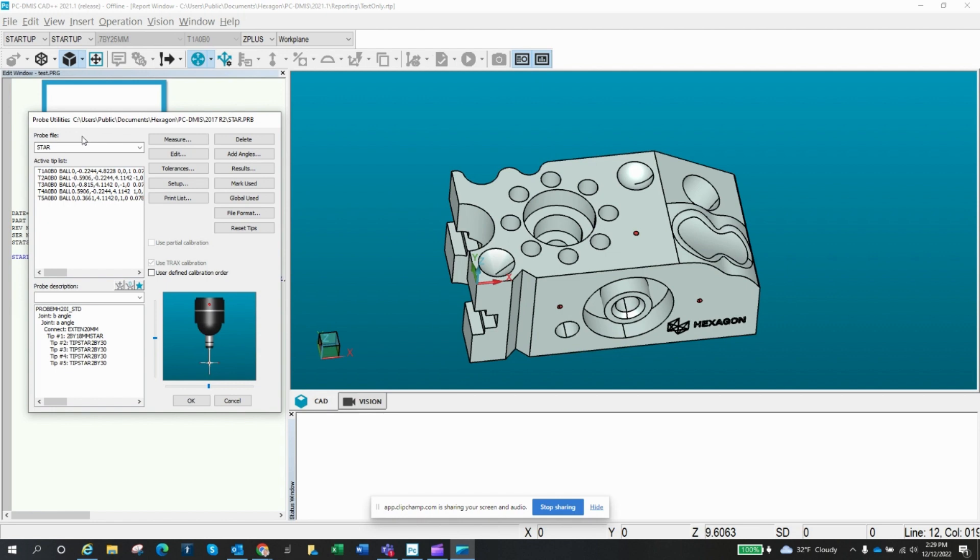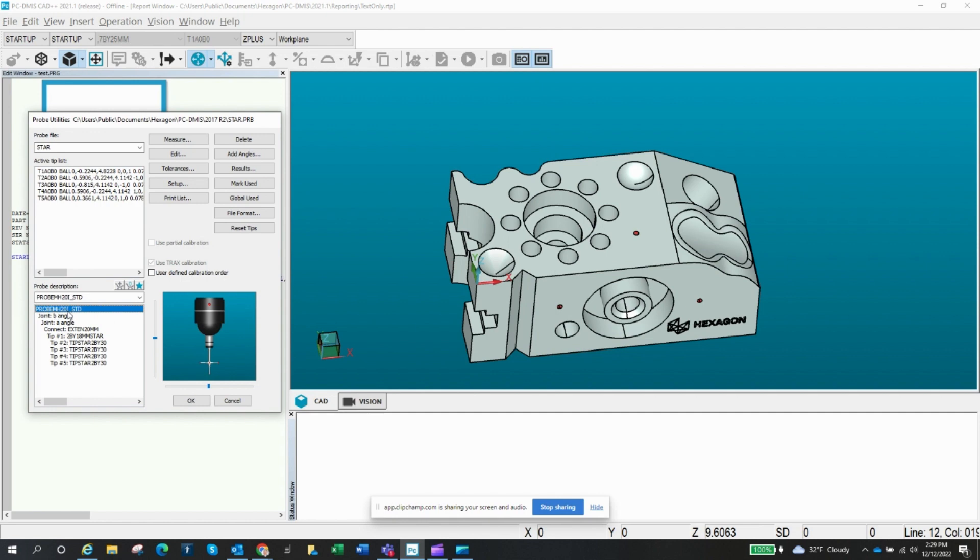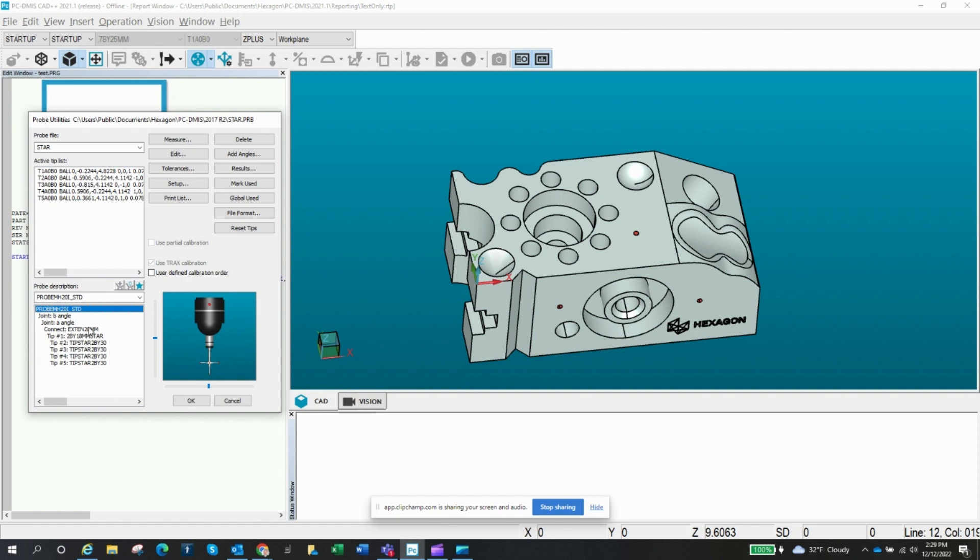If you're not familiar with how to do setup probes, look at another video for that. But basically I'd start out, I just gave it a name. In this case I just called it star. You might call it star two millimeter or whatever you want to call it. And then I happen to be using, I just created one. I happen to choose a Renishaw probe 20i standard. That's this one here. You might have something different, so you might have some different options than what I've got selected here. Because whenever you're creating probes, it does depend on what probe body you're using, whether it's a Tesa, Renishaw, whatever brand that you've got, the choices will be different. And I use this on another program, so that's why I'm just using this probe to show you.